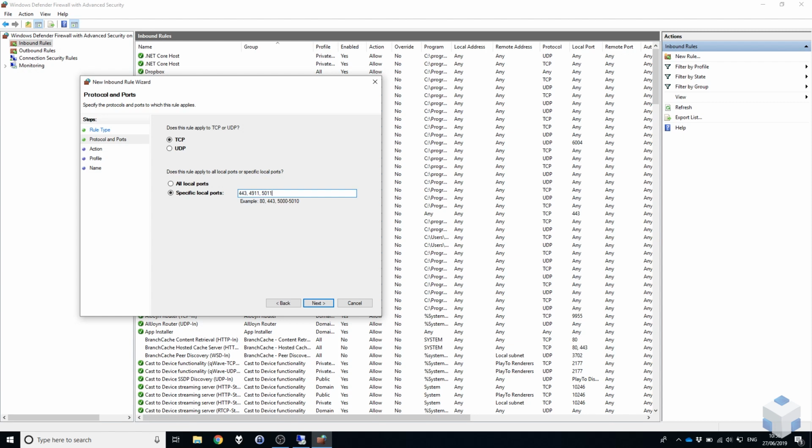So going back a few years, you would have been doing this to port 80, which is standard HTTP, 1911, which is unsecure Fox, and 3011, which is the unsecure platform port. But in this case, secure nowadays, 443, 4911, and 5011 will allow you to connect to your station web server over HTTPS.